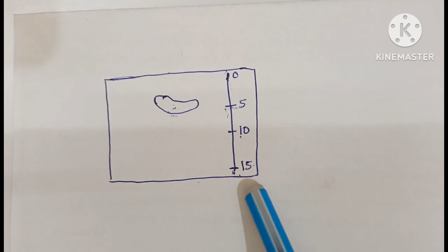By decreasing the depth up to 5 centimeters, it not only increases the size of the image, it also increases the clarity, increases the resolution of the image, and increases the frame rate of the image. Remember, by decreasing the depth, you increase the clarity, resolution and frame rate. Increase the frame rate, and a better image will be produced.